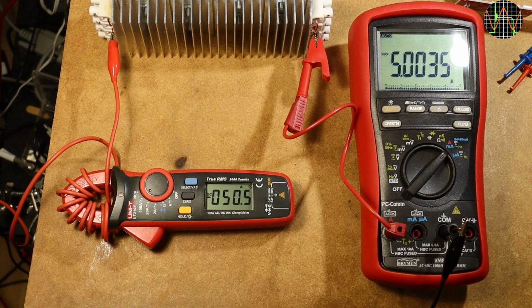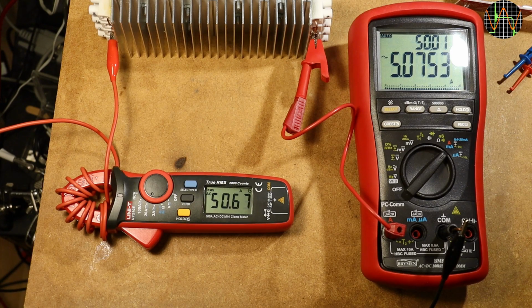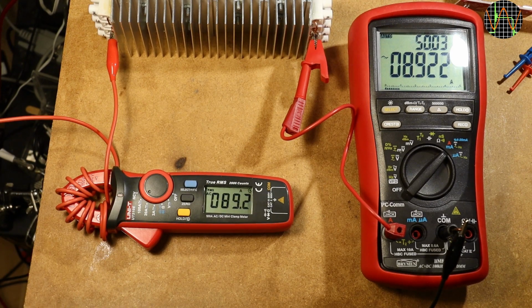A similar test for the AC currents. 31.6 amps in the 20 amp range, 50.7 amps in the 20 amp range. Testing the 100 amp range shows 50.7 amps as well. And now we read correctly 89 amps in the 100 amp range.